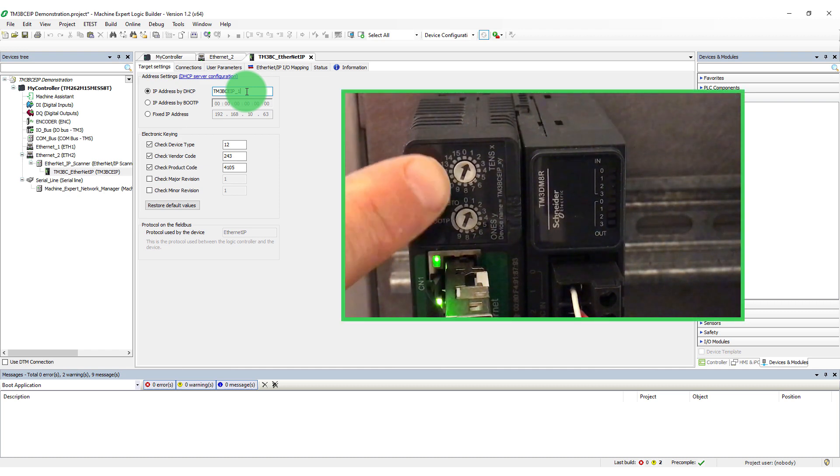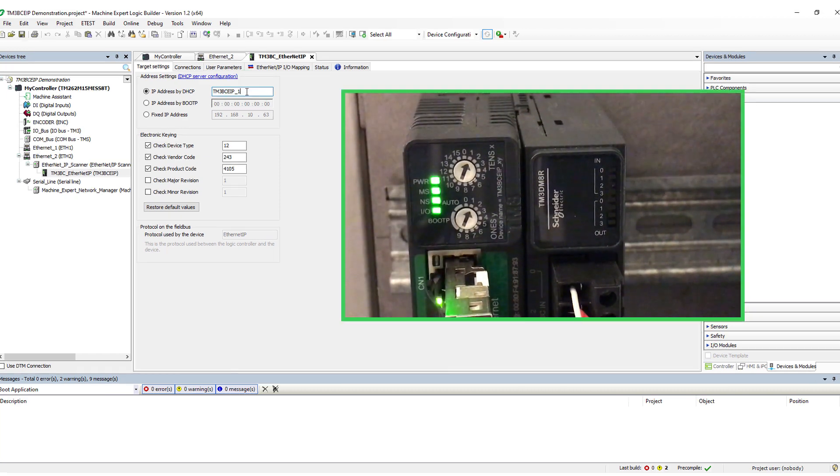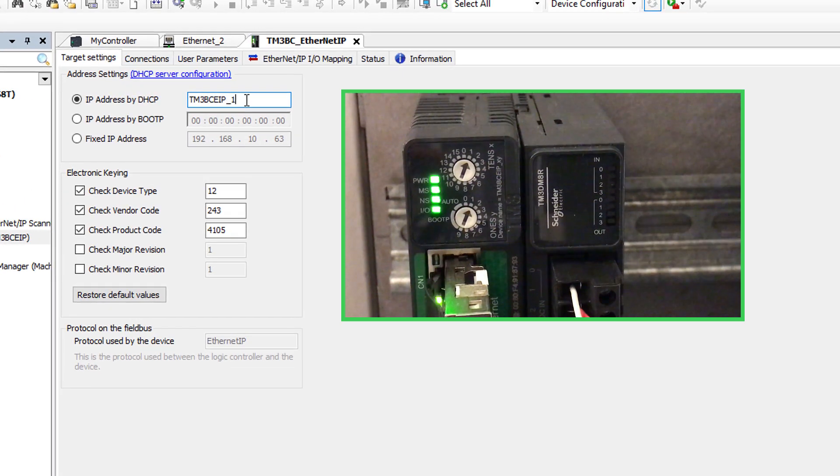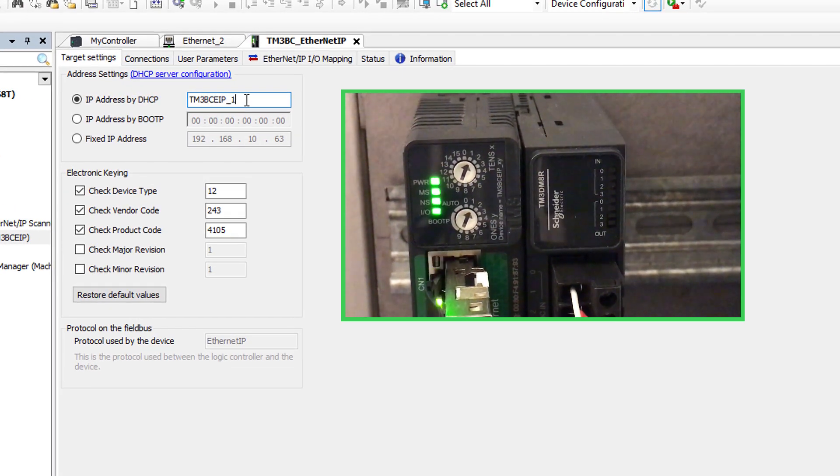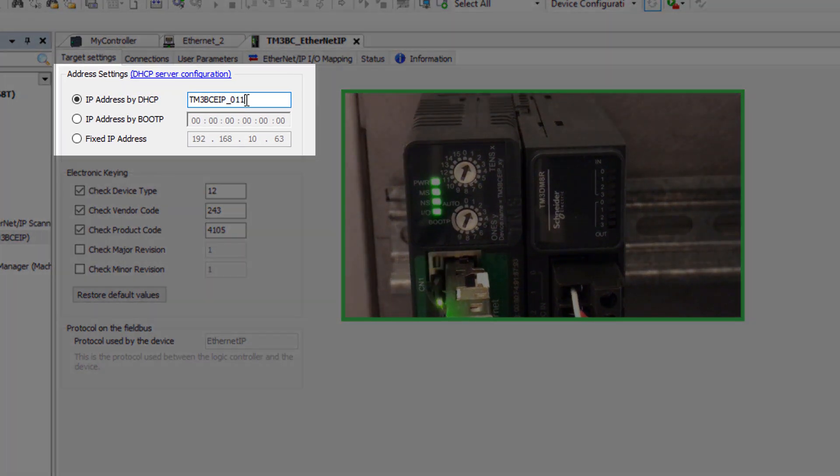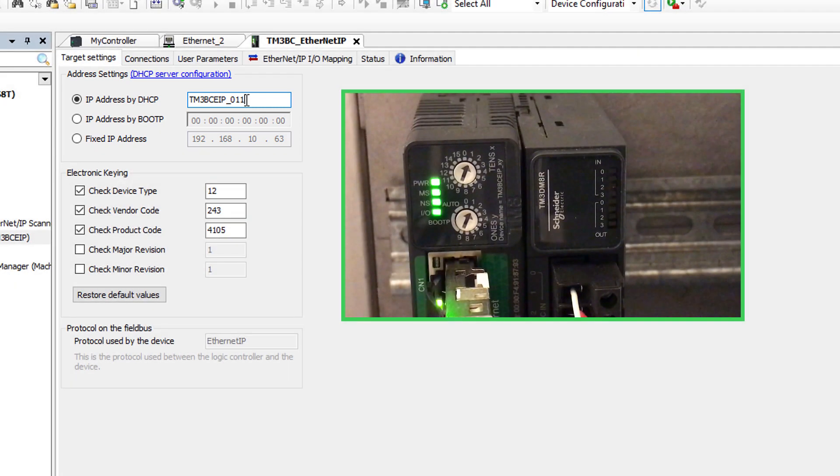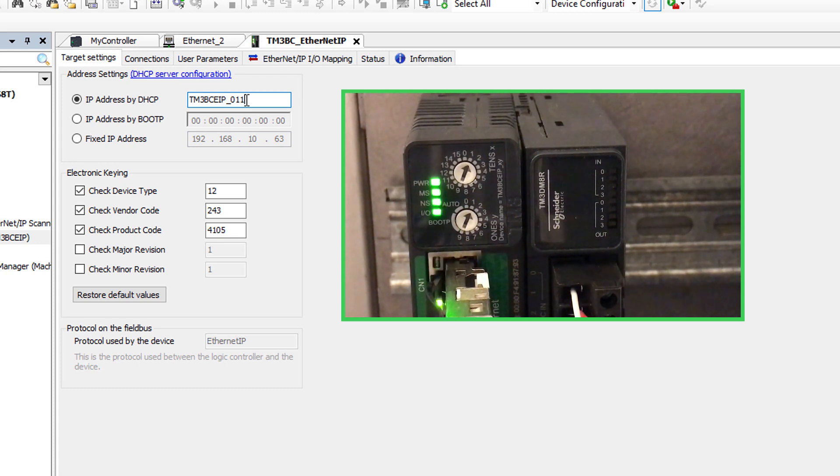Set the name according to the switches on the bus coupler. The name format must be TM3BCEIP underscore, followed by a three-digit number. For example, the address 11 is TM3BCEIP underscore 011.